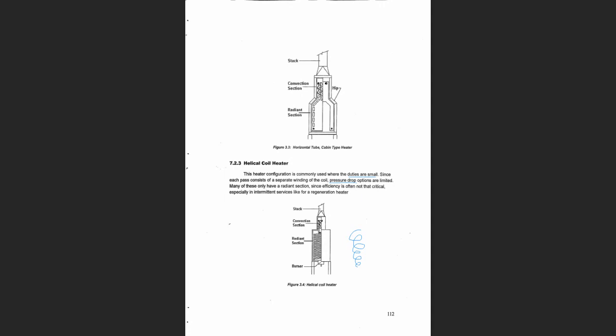تخيلوا هذا البروسيس فلويد داخل من هنا، وطالع من هنا مثلا على سبيل المثال. لو تقيس الضغط هنا في المنطقة هذه الأولى قبل P1 نسميها، وقست هنا P2، حتى لو كان الفيرنس نظيف if the coils are clean يا شباب you'll see that there is a huge pressure drop، في انخفاض كبير في الضغط يا إخوان. طبعا ليش البريشر دروب يعتبر دائما سيء؟ يمكن ذكرناه في أكثر من مناسبة يا إخوان.